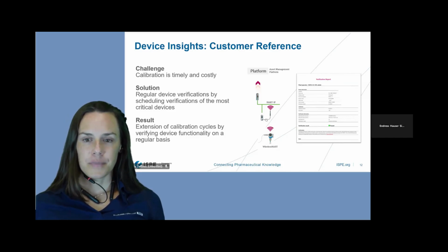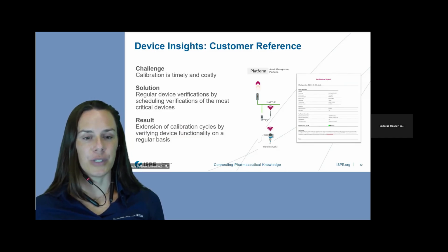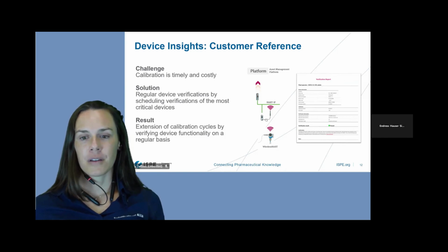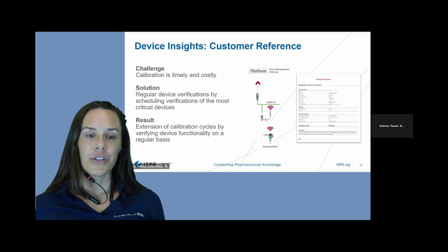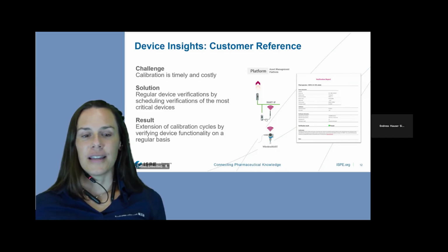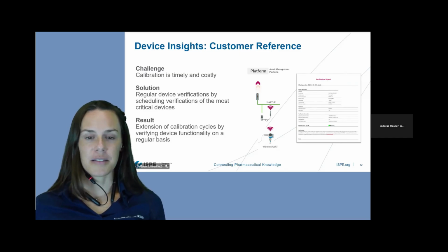In this case, the customer was able to extend their calibration cycles by doing verification once per month. These asset management systems let you schedule verification, which then runs in the background, and you get notified if there's any issue with the device—significantly reducing the time devices are out for calibration.